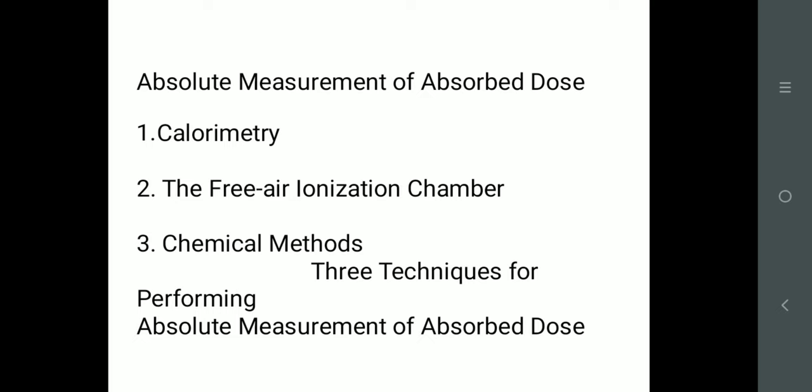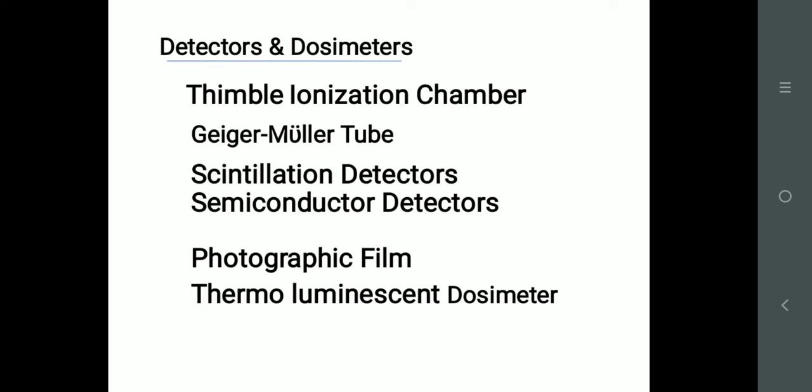To measure absorbed doses, we have calorimetry, free-air ionization chamber, chemical methods mostly used in departments, and detectors for area monitoring: thimble ionization chamber, Geiger-Müller counter, scintillator detectors, semiconductor detectors, photographic film badge, TLD, OSLD, and pocket dosimeters. Recently we are having GafChromic meter — like litmus paper, you keep the paper and the color increases as per the dose. We have bubble test: load a syringe with bubbles, keep it in the radiation area, and the more the bubbles, the more the ionizing radiation. And MOSFET detectors — Metal Oxide Semiconductor Field Effect Transistors — are also used.